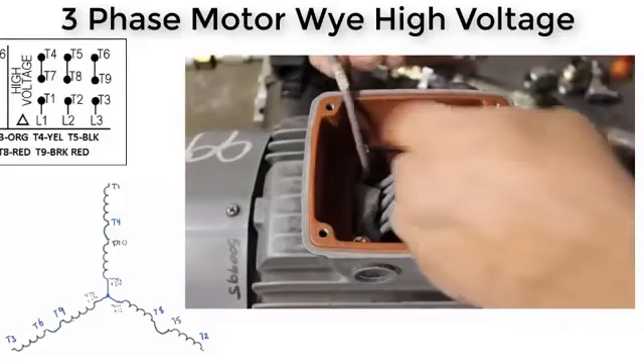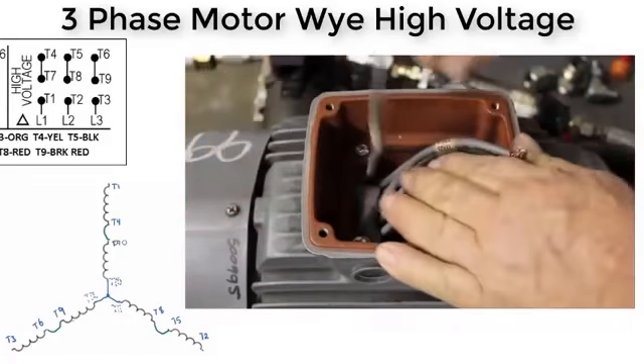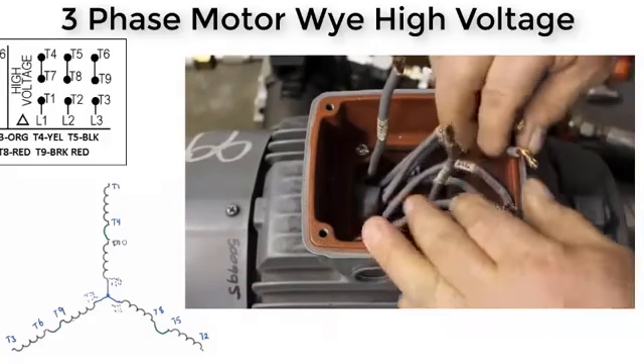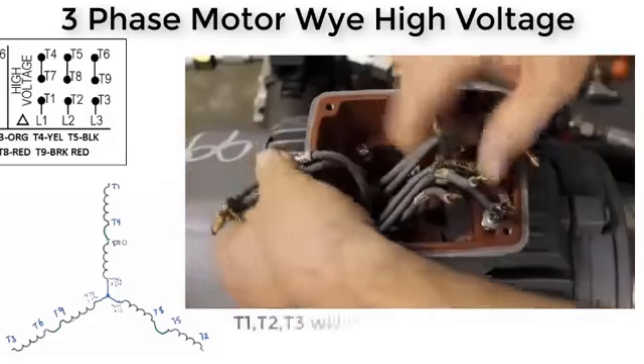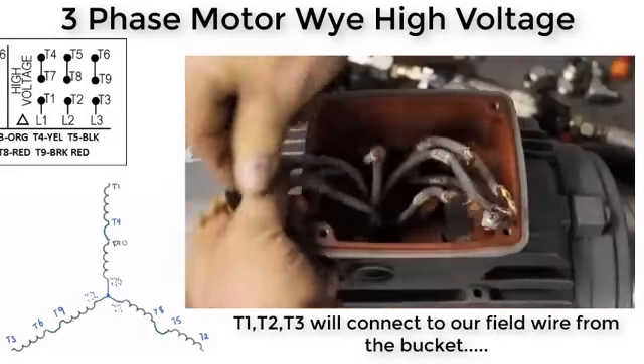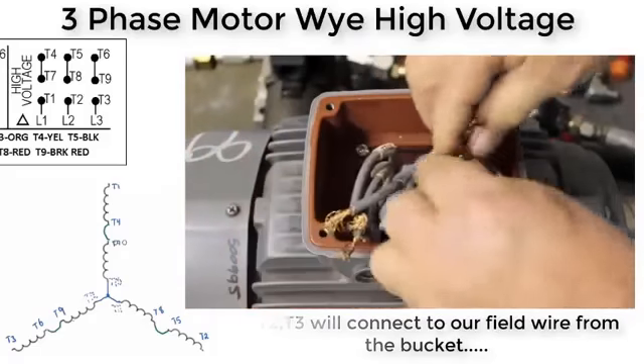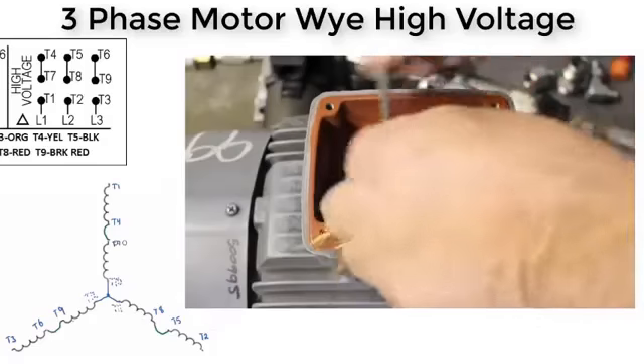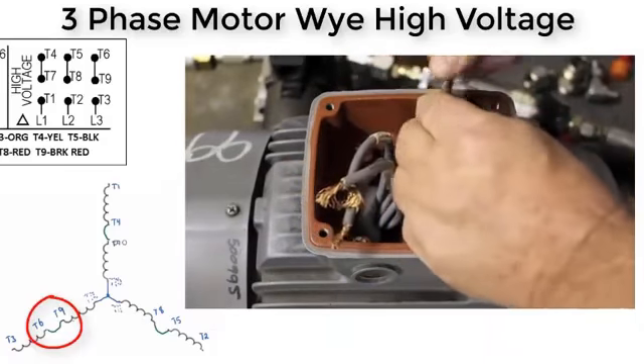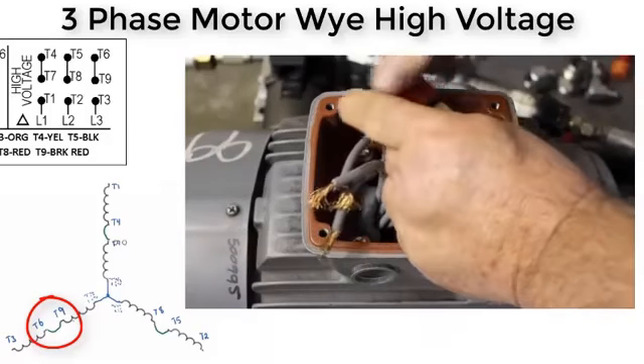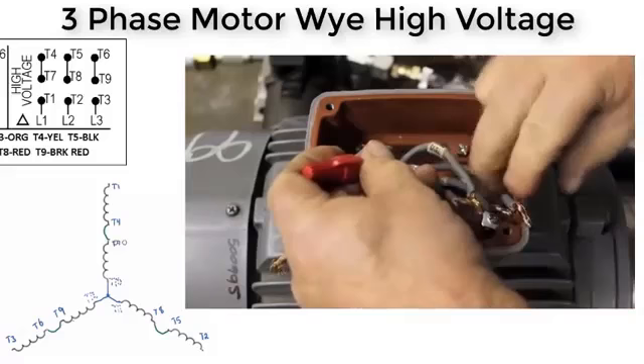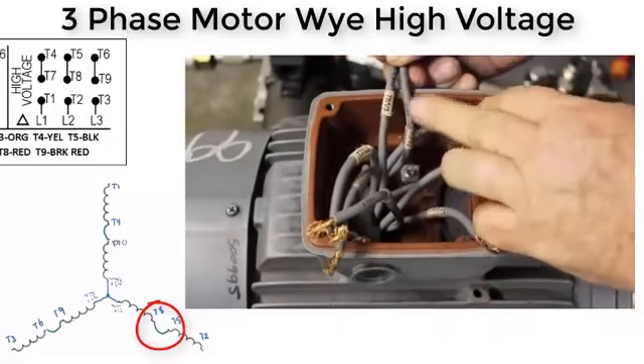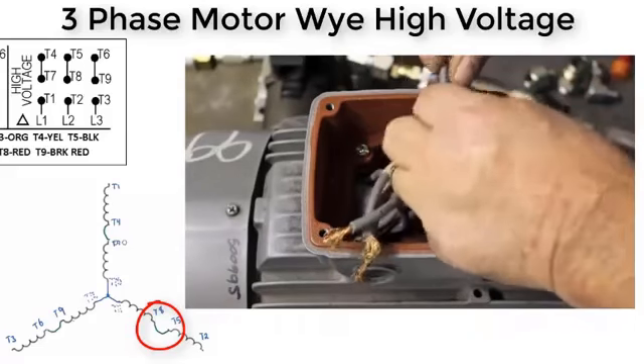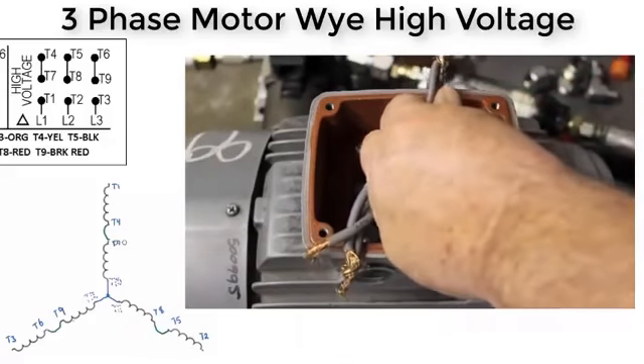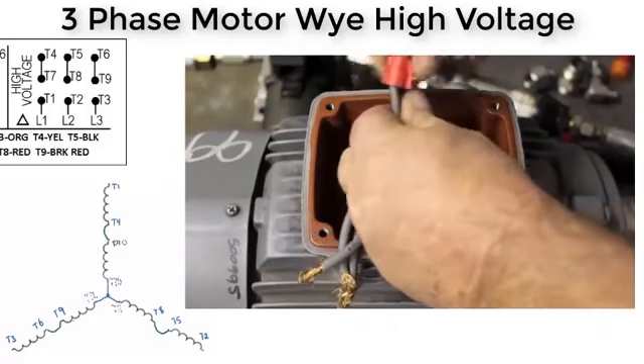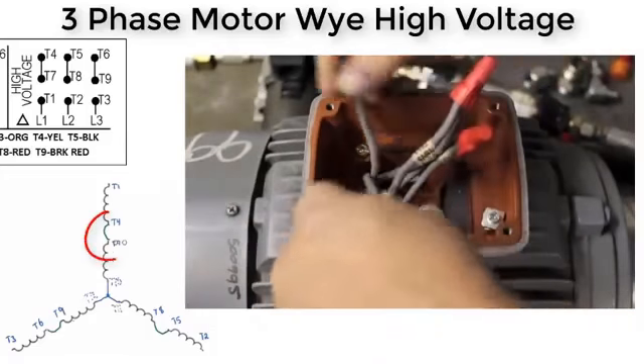Take wire 1, set it aside. Find wire 2 or 3, doesn't matter, get them out of the way. That's wire 2, tuck them out of the way. Then you're going to find 6 and 9, wire them together with a wire nut. You're going to find 8 and 5 -- there's T8 and T5 -- wire those together with a wire nut. Seven and 4, that's your last combination.